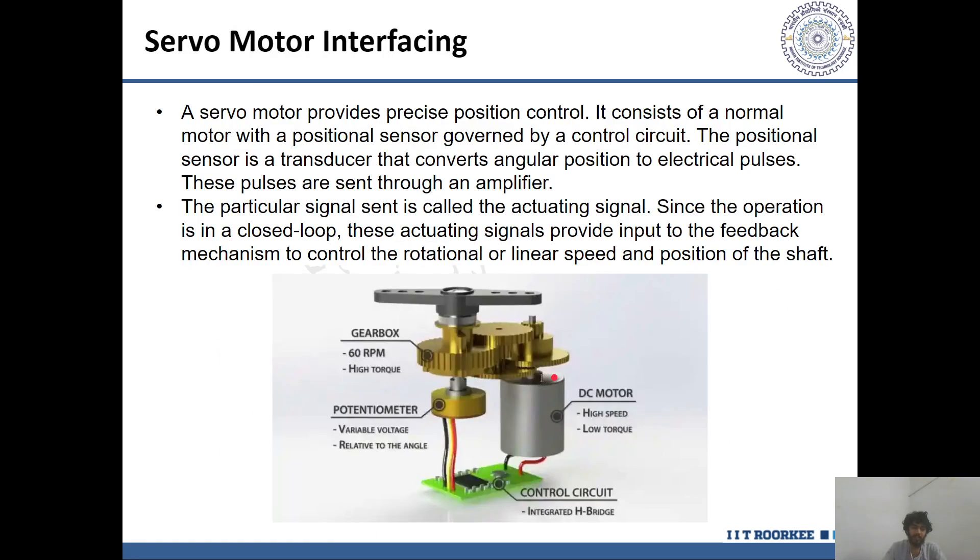Now, talking about the servo motor. A servo is basically a combination of motor, a shaft, a gear assembly, an amplifier and an encoder. It is a self-contained electrical device that rotates a machine or parts of a machine with very great precision and high efficiency. By controlling the position and the speed of the shaft, we can control the angle of the shaft with respect to stationary parts. The servo consists of a normal DC motor with a positional sensor which is governed by a control circuit such as an H-bridge. The positional sensor is a transducer that converts angular position to electrical pulses. These pulses are sent through the amplifier and are also called actuating signals. Since the operation takes place in a closed loop, these actuating signals provide input to the feedback mechanism to control the rotational or the linear speed and the position of the shaft of the motor.